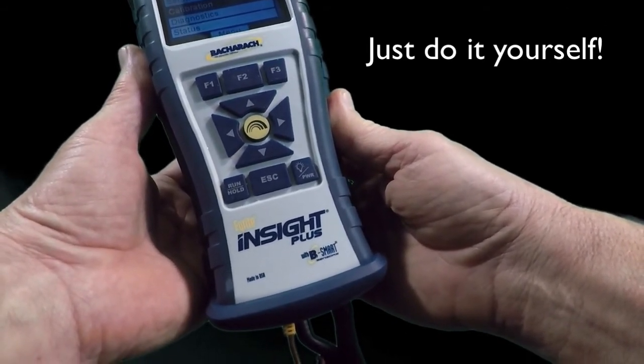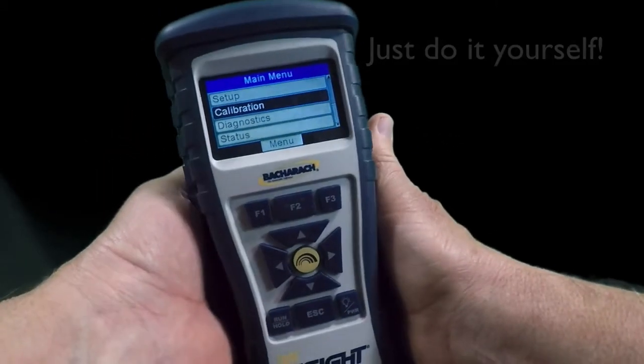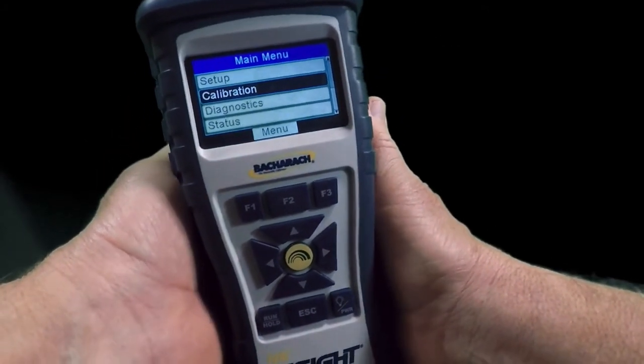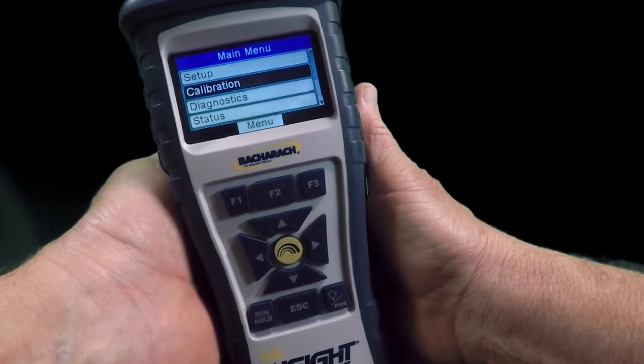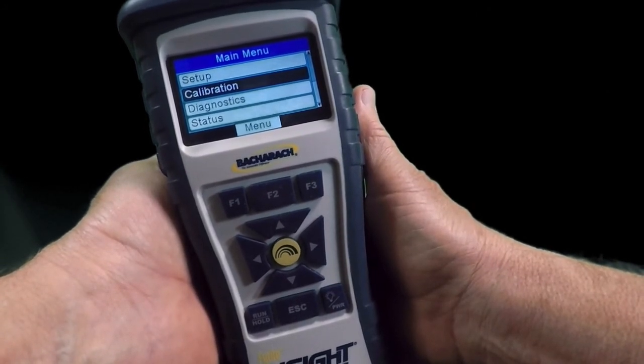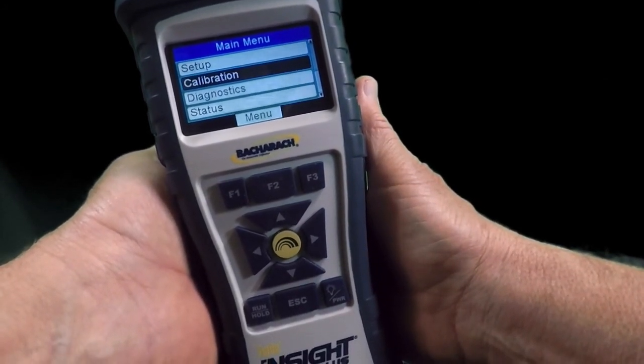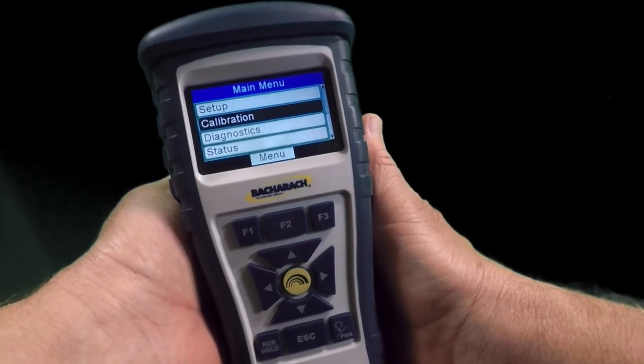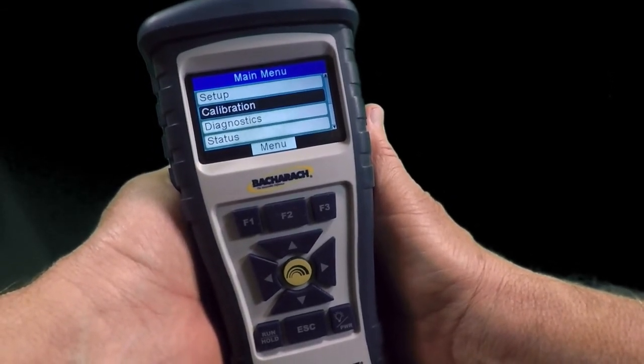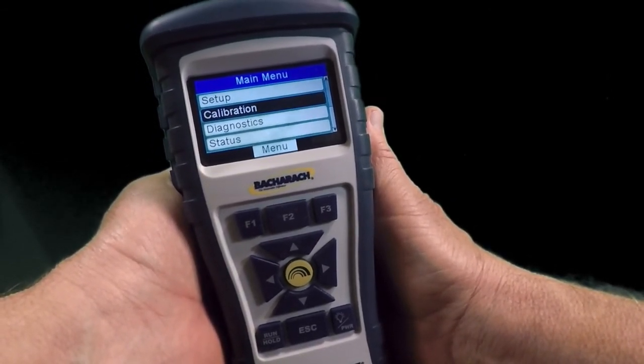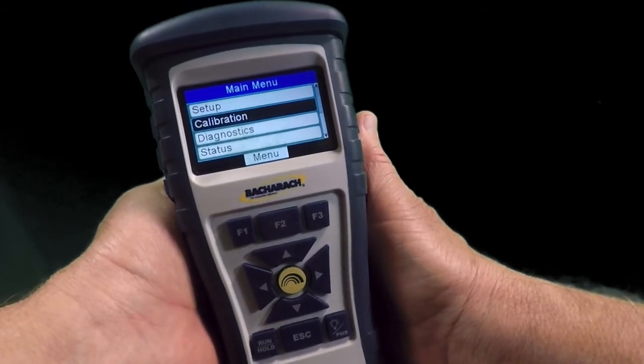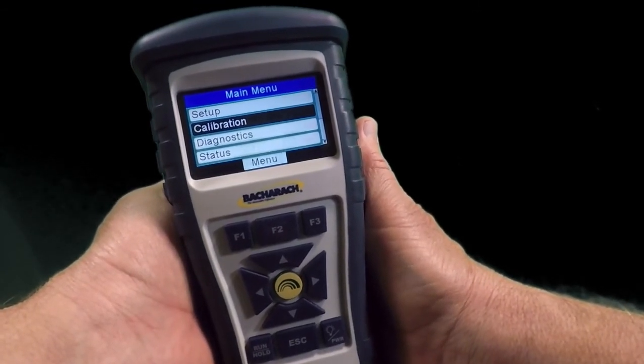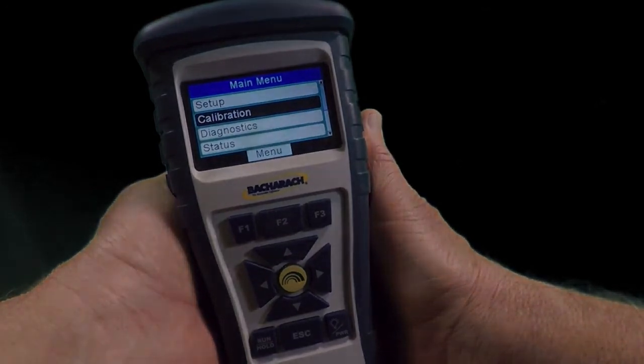Now, the other advantage to having a calibration kit on site is that if you have any reason to suspect that the readings might not be correct, you can always slap some gas on it and check to see. I would suggest looking at what's called a demand regulator. That's usually the easiest and most economical way in terms of gas to do the calibrations.